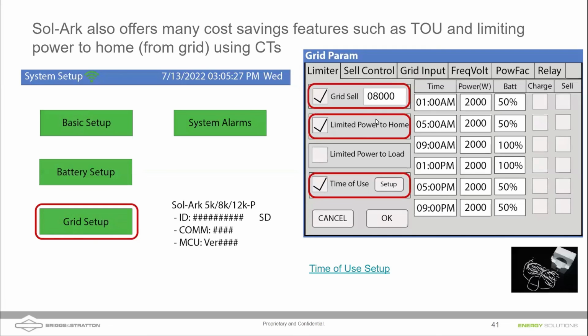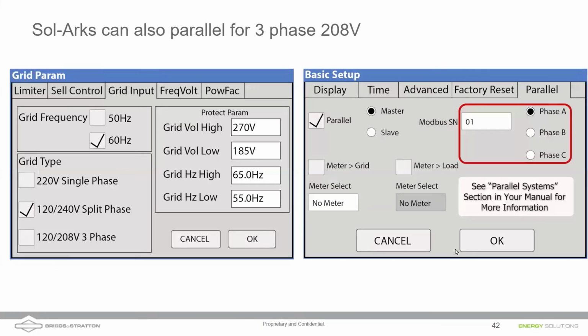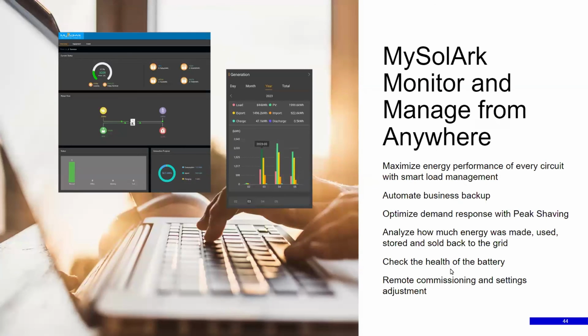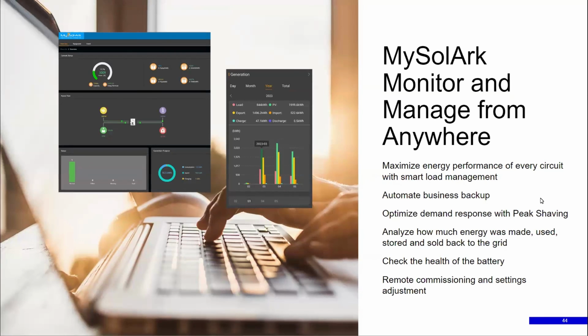And as far as providing the fuses when you're combining multiple inverters or multiple batteries, what I would argue to inspectors is that, look, this is a listed system for multiple inverters in parallel. Sol-Arks have a UL 1741 CRD power control system, which technically applies to the AC bus bar monitoring and control, but it is monitoring current along the bus. The reason why you fuse DC bus bars when combining multiple batteries together, given that both the battery BMSs and the inverters have overcurrent protection already built into them in some way, shape, or form, is mainly that the combining point has such a short potential that you have to throttle down the interrupt rating. Your millisecond short circuit interrupt rating can overwhelm the bus bar terminals.